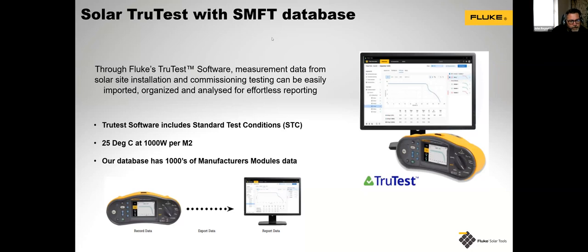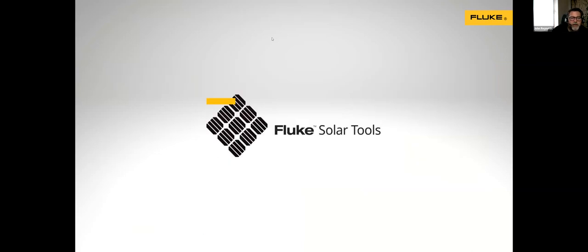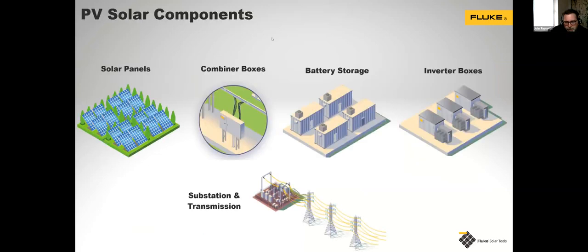Just for reference, the standard IV curve is taken at 25 degrees at 1000 watts per meter squared of solar radiation. Obviously, that's not going to happen every day, but you can compensate for that. So let's move in. Where are we going to be using Fluke test tools? Well, we can see that we've got solar panels, combiner boxes, battery storage, inverter boxes, and in certain situations we may be near or involved in substation and transmission. So we've got tools that will be able to do all of that.